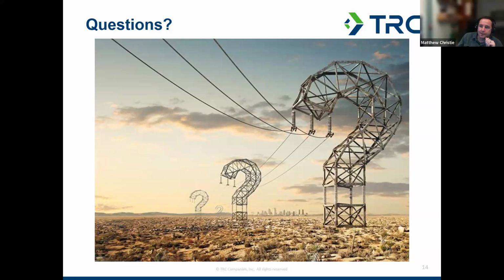No. With a heat pump water heater, there's a coil that flows into it, but instead of electricity coming in, it's sending in hot refrigerant inside that copper coil. It draws heat out of the air, compresses it, warms up the refrigerant, squishes that heat into a smaller volume like a pressure cooker to make it hotter, then runs that hot refrigerant through the water inside copper coils. The heat dissipates out and the cycle repeats. So those won't burn out anodes, there won't be any issues there.